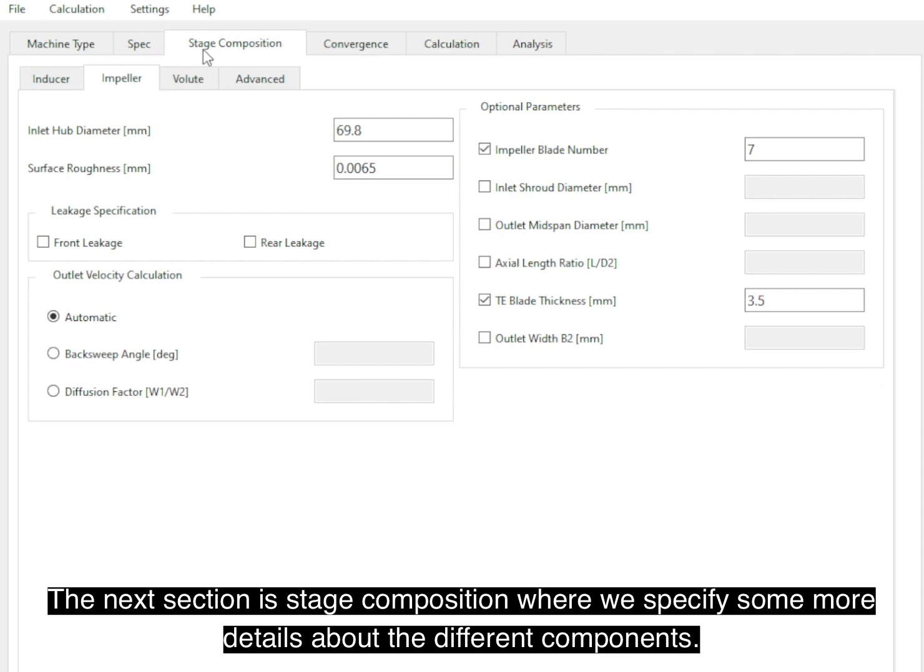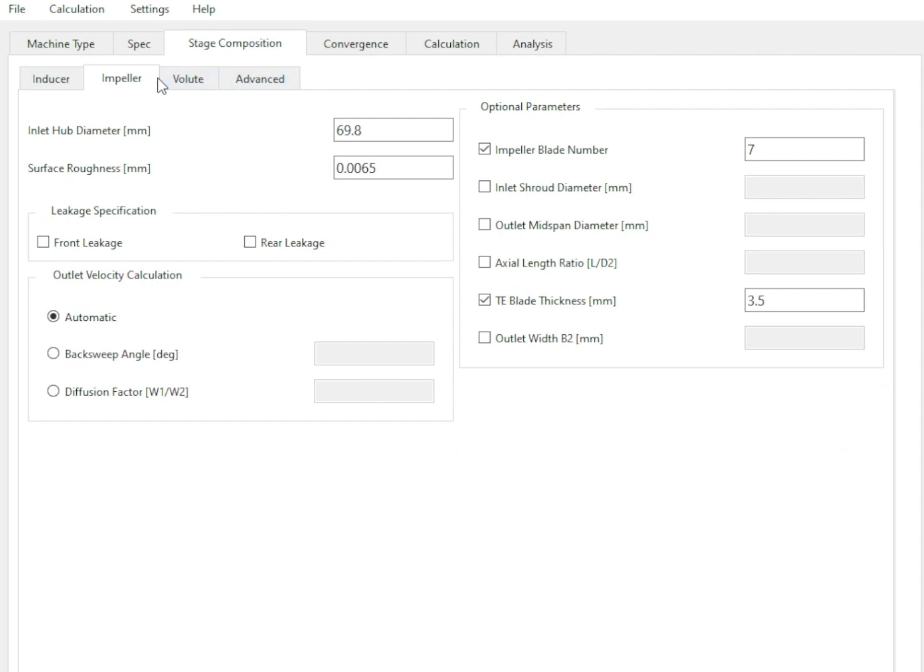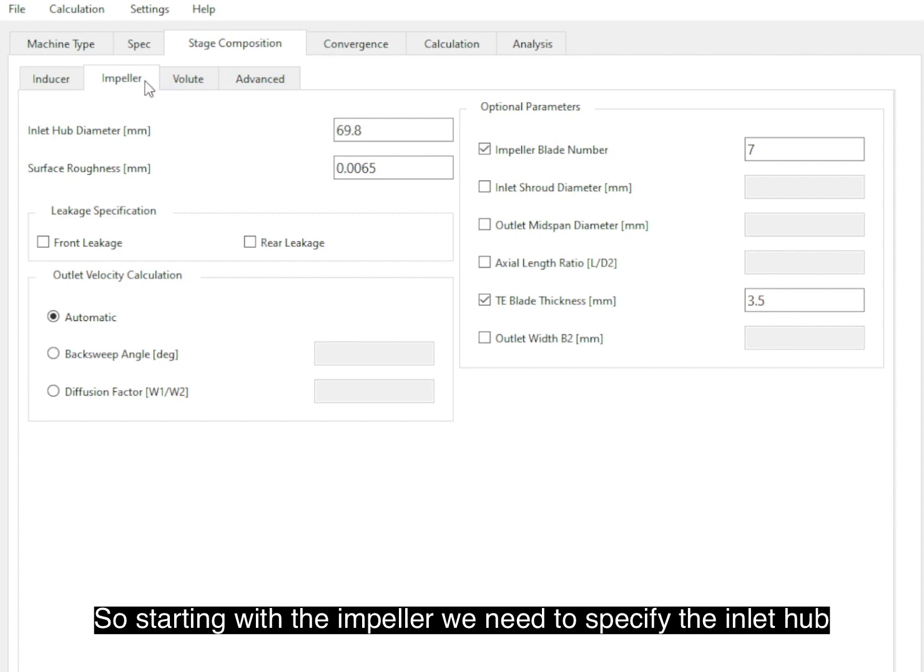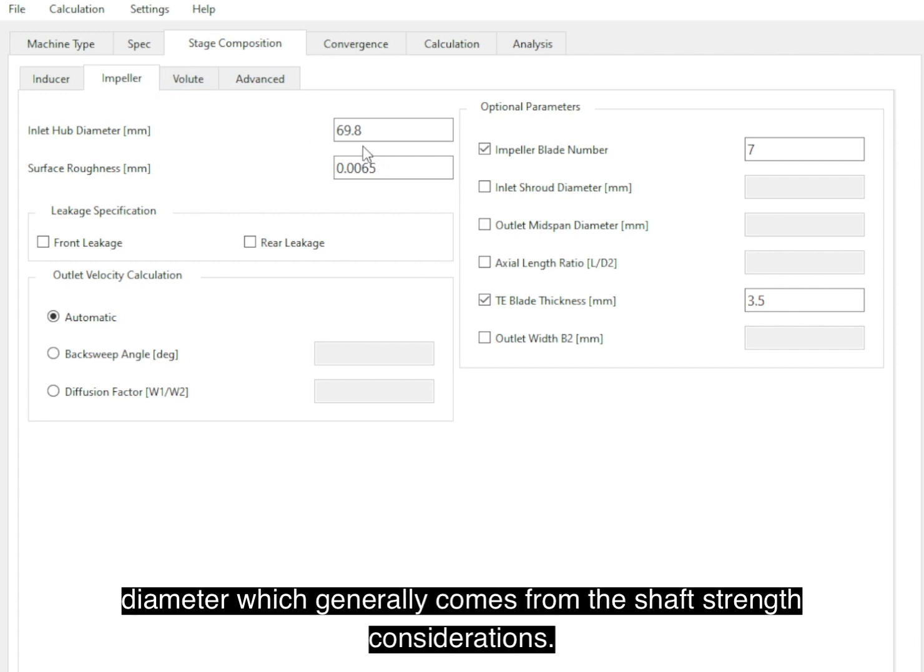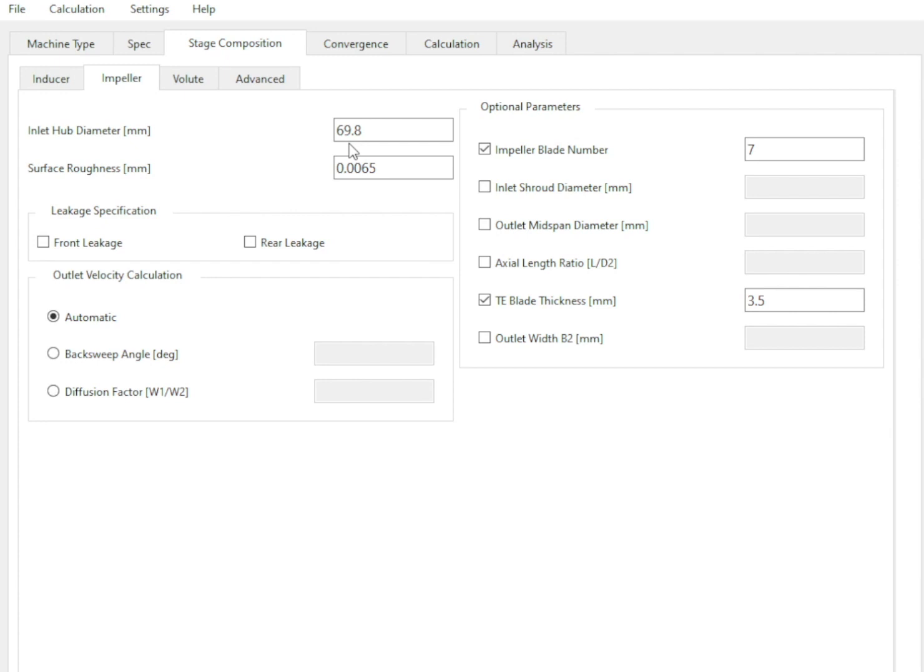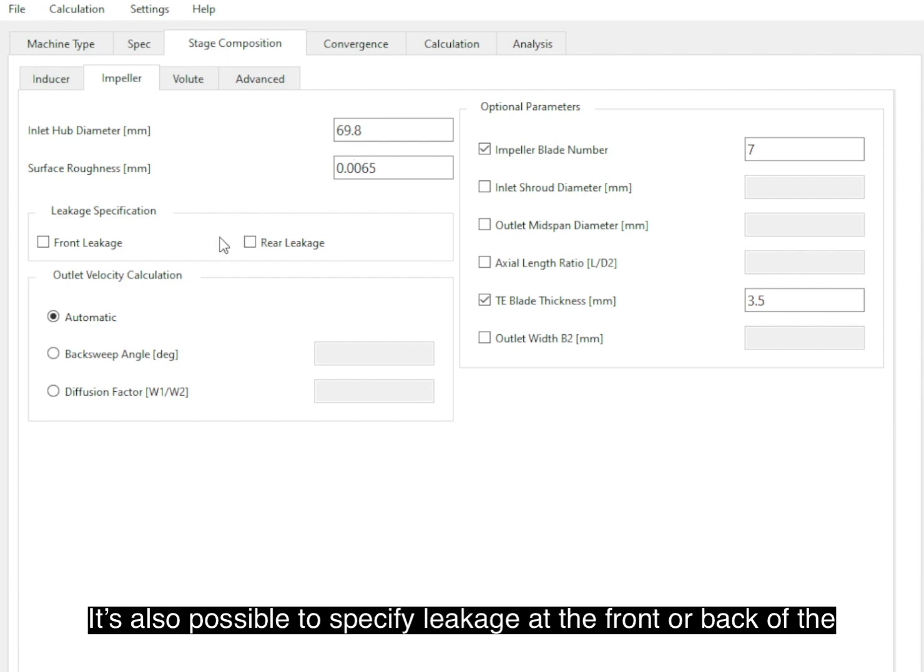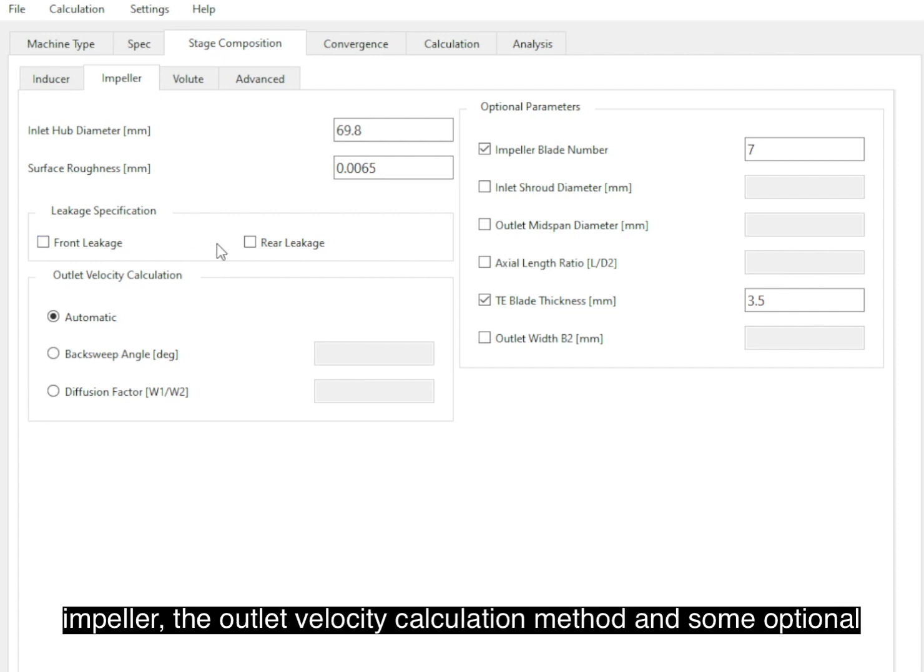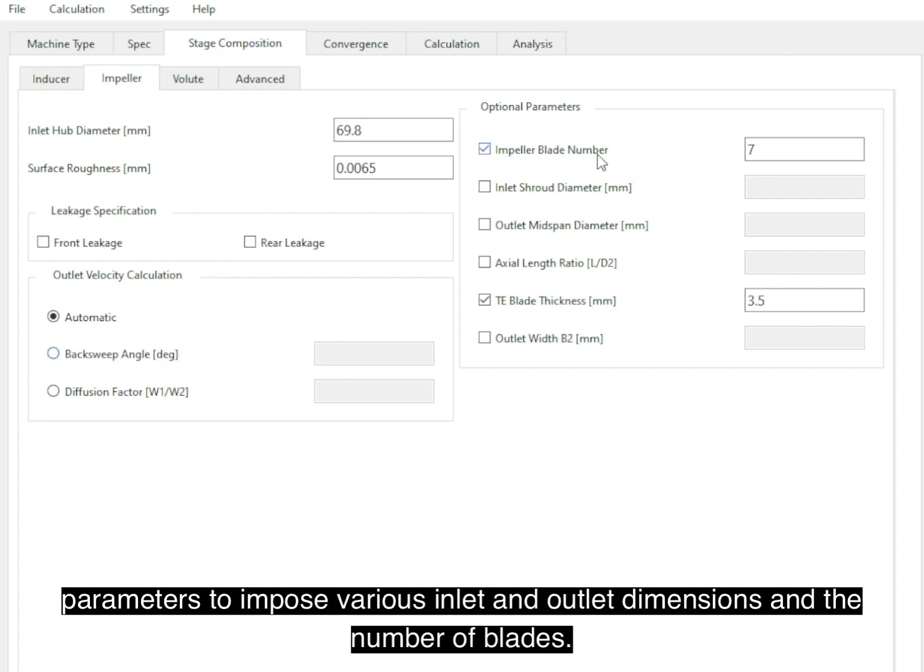Where we specify some more details about the different components. So starting with the impeller, we need to specify the inlet hub diameter, which generally comes from shaft strength considerations. It's also possible to specify leakage at the front or back of the impeller, the outlet velocity calculation method, and some optional parameters to impose various inlet and outlet dimensions.